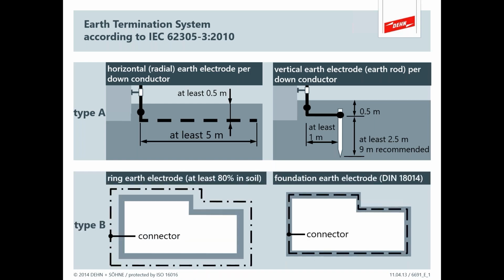The earth termination system really isn't that much different. You still have to pay attention to all the other aspects of the electrical system. What's nice about the IEC methods, again, here I'm showing that you have options for what you can realistically do at a site. Picture this, maybe this building is surrounded by concrete, and you're going to be very challenged to get a lightning rod, an earthing rod, in the first place, let alone build a ring. So there are things you can do with your lightning earthing system.